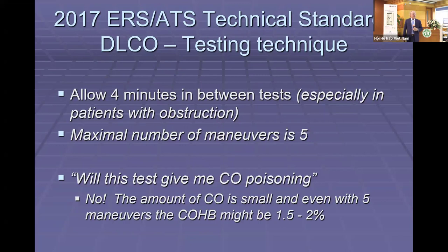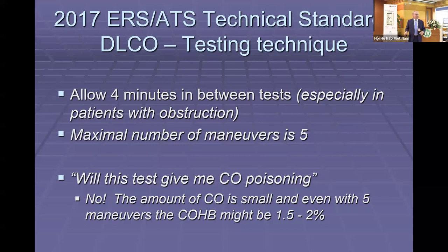You should allow about 4 minutes between tests. If you have a rapid gas analyzer, you just need to make sure the test gas returns to baseline before doing it again. But in general, because you want the gas to wash out of the lungs, and by the time the patient and system are ready, it's typically about 4 minutes between maneuvers anyway.